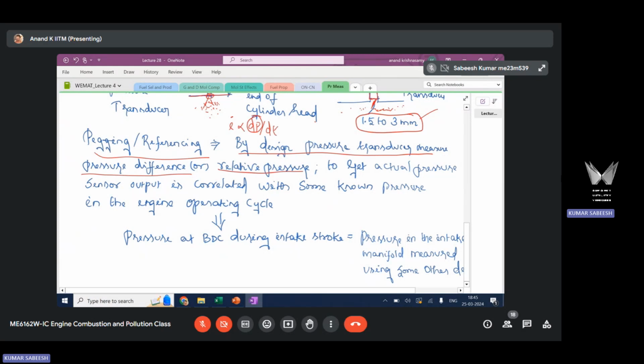It will take some arbitrary starting point. The arbitrary starting point may be the point at which the sensor gets started or reset. That is an arbitrary time instant. The signal output from this pressure sensor goes to an amplifier, and the amplifier has an integrated circuit. That integrated circuit will integrate the input current value over a period of time. So it starts from some arbitrary pressure value or arbitrary time instant. That is how you get dP here.